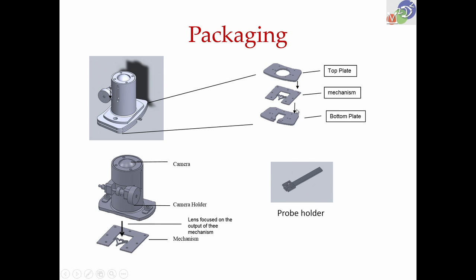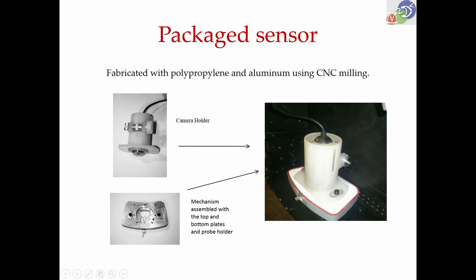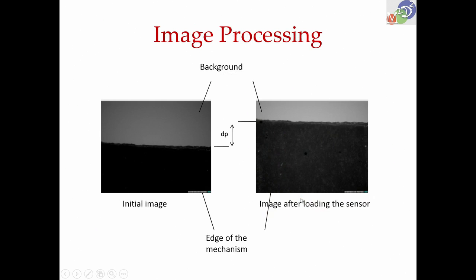And as I said, this works more like a cartridge, where the middle one is the one you can replace if it breaks. There is a little holder to hold a glass probe, glass needle, or pipette as it is called, to attach to this. That is going to fix and probe the cell to apply force. So, now we see this probe holder, to which you will attach a pipette. This is all with aluminum. It is quite big. The digital microscope will be about an inch in diameter and 4 or 5 inches in length. So, it is a bulky device, but can measure very small forces.